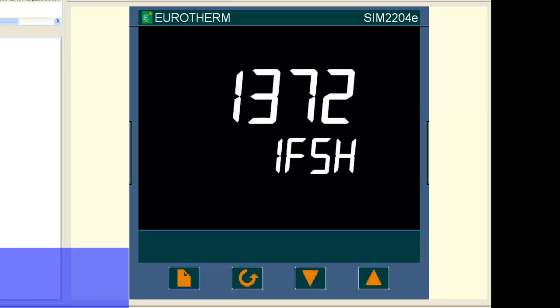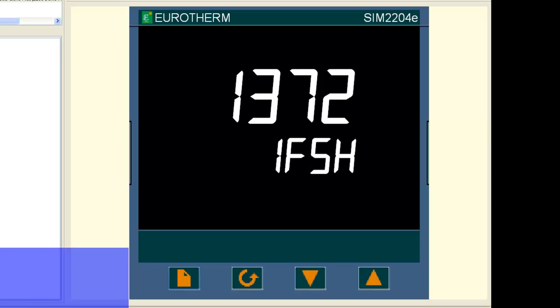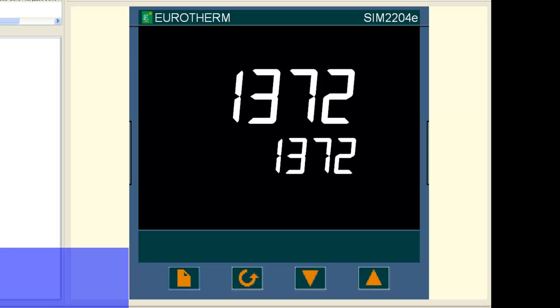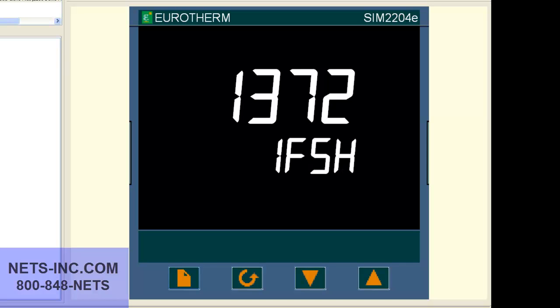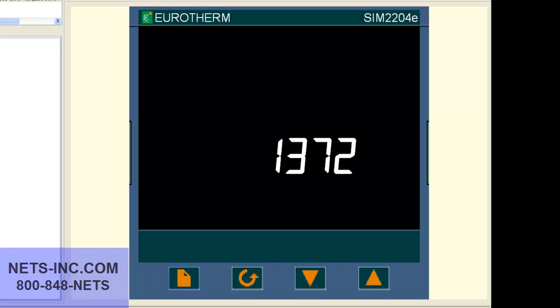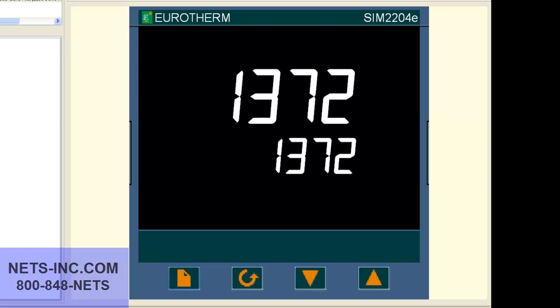We first begin by putting the controller into the configuration level. Please note, when putting the controller into the configuration level, all outputs are shut off from the process. Before doing this, make sure it is safe to do so. We will be using the four buttons across the bottom of the controller.